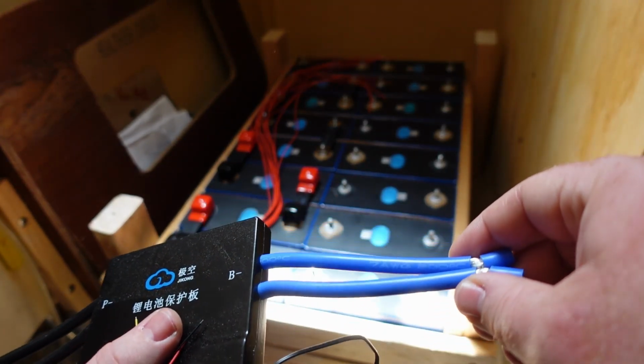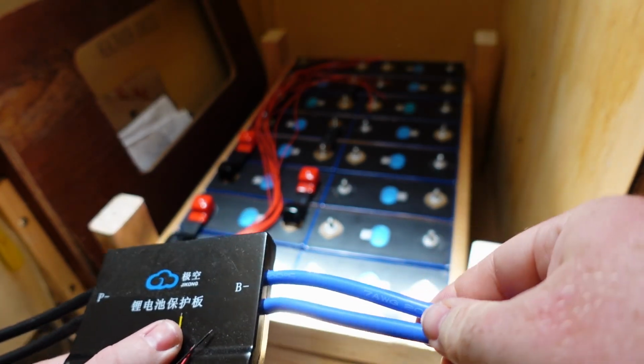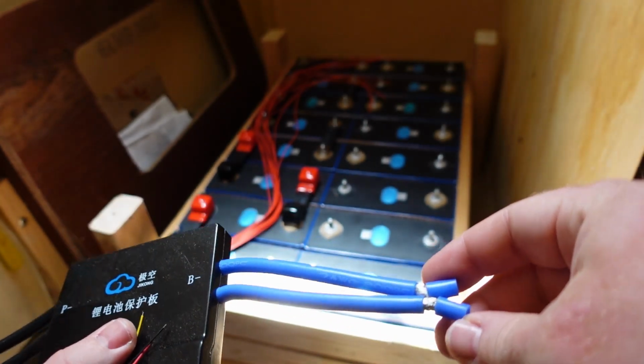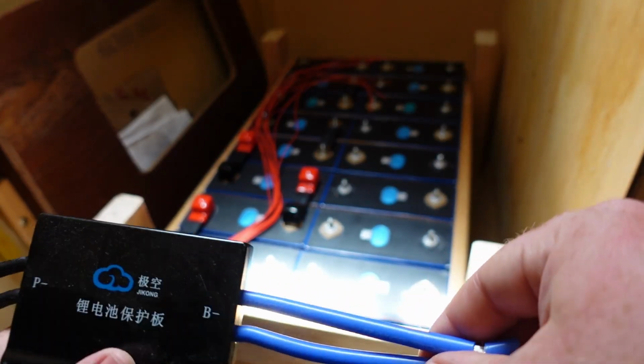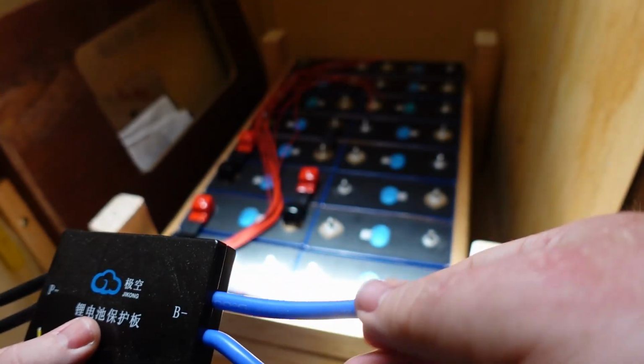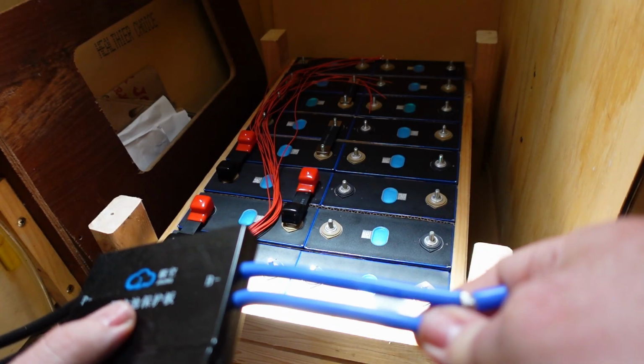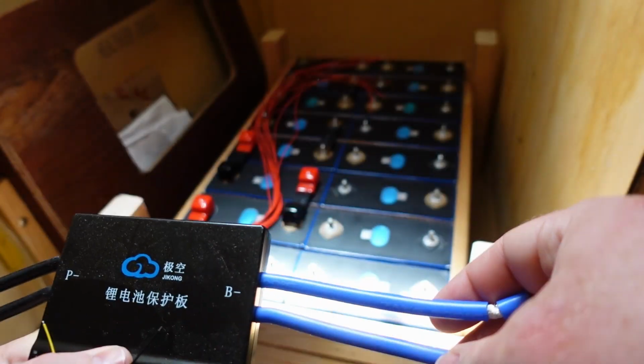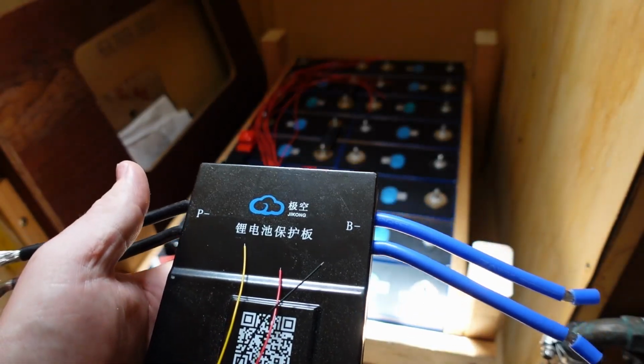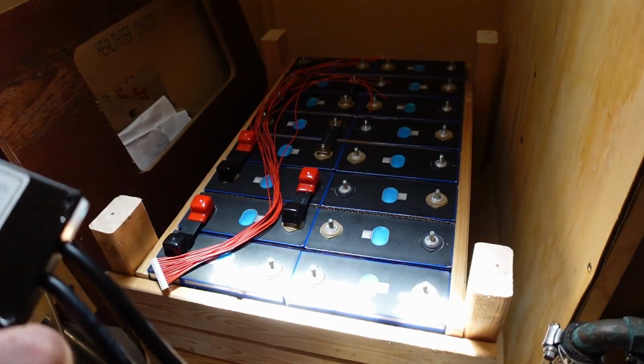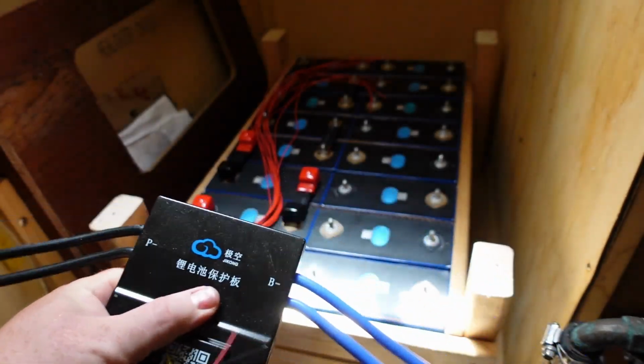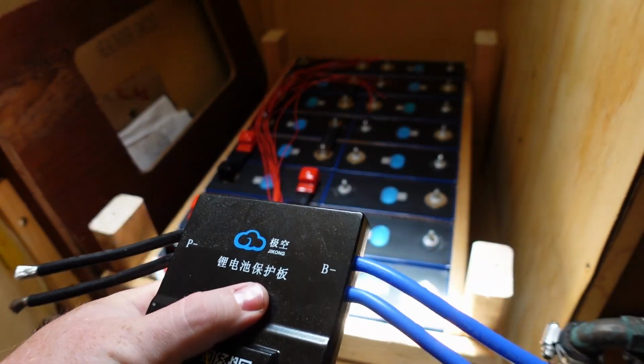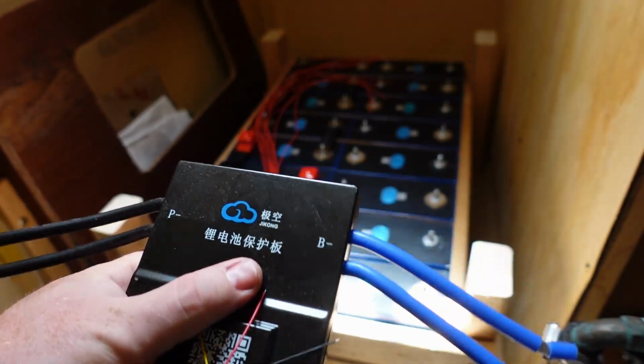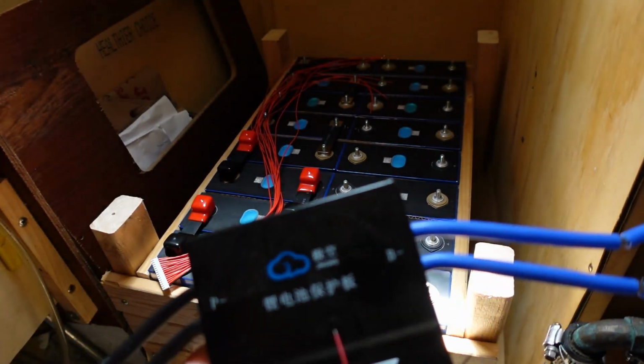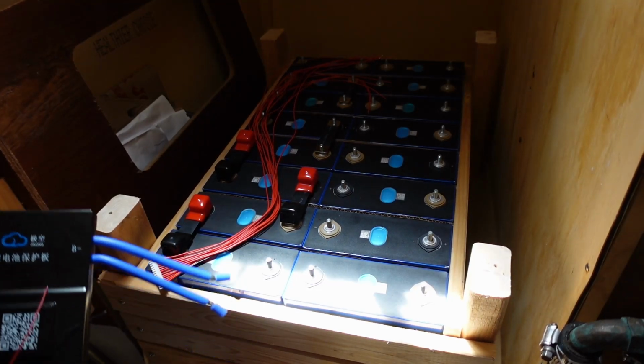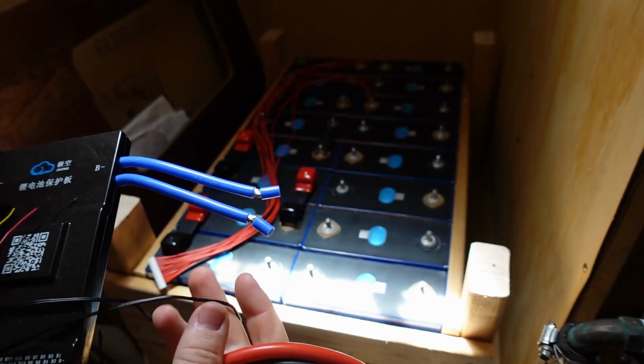They got two of them. So two together, if you were to look up how much current you could put through these wires, still doesn't quite add up to 200 amps. It falls a bit short. But because of the high silicone temp rating of this gauge wire, a lot of people have tested this BMS under 200 amps and it handles it just fine. Running it continuously at 200 amps is probably not the best, but it can do it. So I've gone up a little bit to 6 gauge, which will give me a bit more margin.